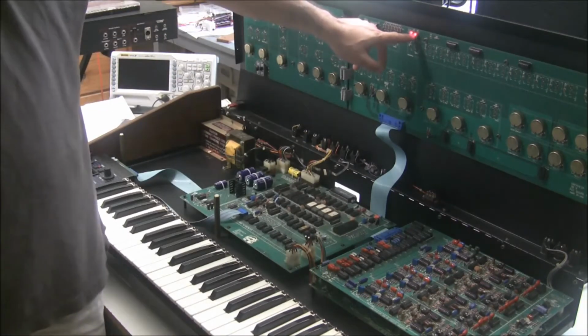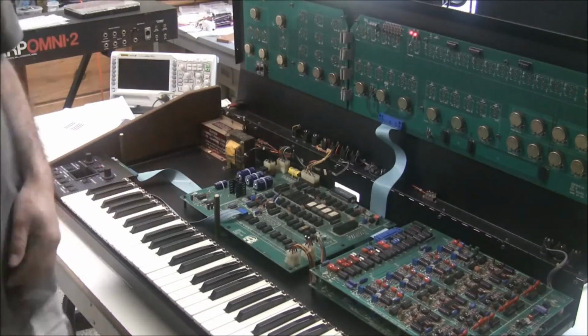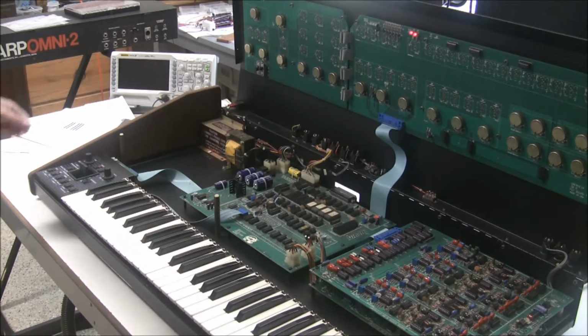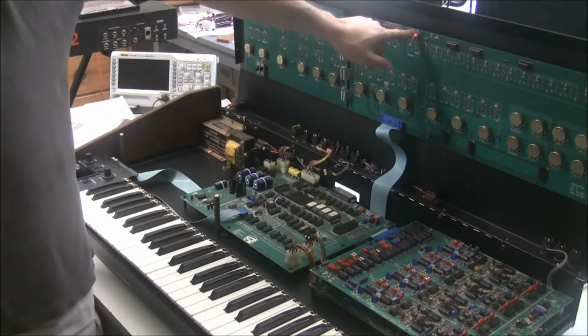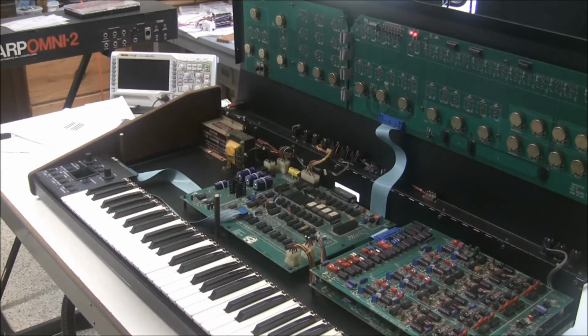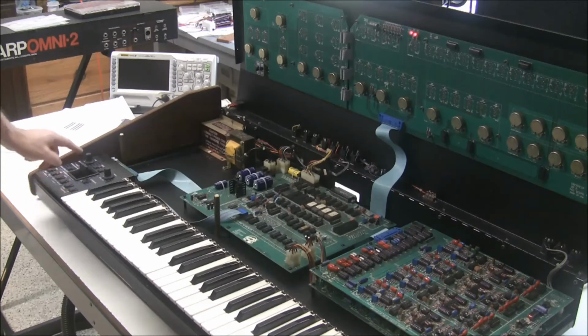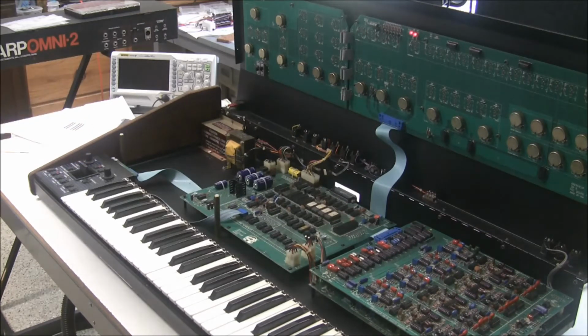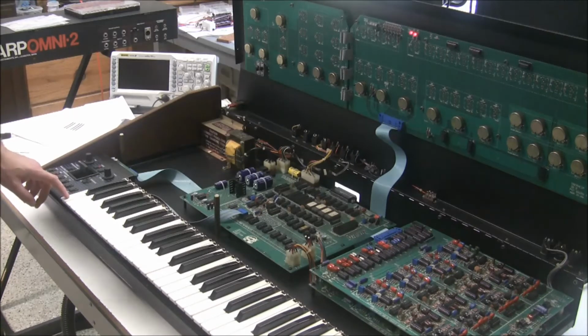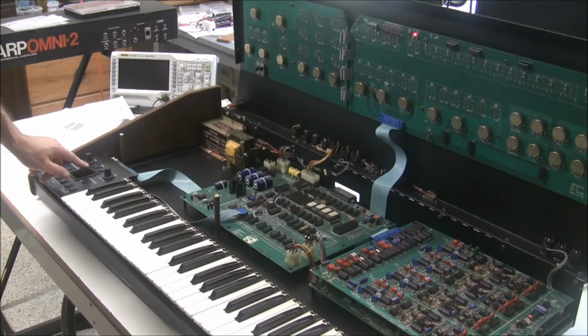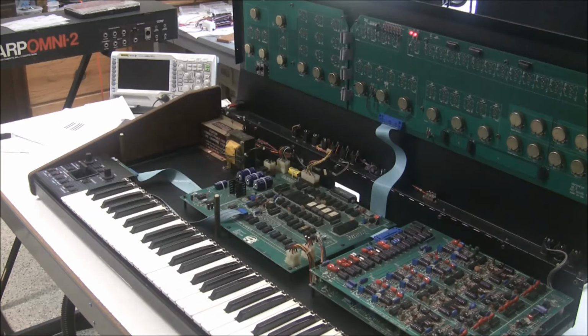So there's these two LEDs up here, and if only one of them is lit, then it's not in calibration, and you need to tweak the trimmer until you get both LEDs on. When both LEDs are on, the microprocessor says that this is calibrated. So I hit the C key, and you can see as I move this lever, it believes that there's an offset, and then I need to calibrate it. But when it's in the middle, both LEDs are on. And then I'll hit the D key, and this lever is also in calibration. Again, as I move it off the center, it thinks that there needs to be an offset added to center it. But when it's resting in the center, this is calibrated.